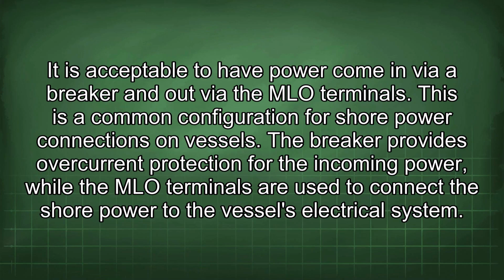It is acceptable to have power come in via breaker and out via the MLO terminals. This is a common configuration for shore power connections on vessels. The breaker provides overcurrent protection for the incoming power, while the MLO terminals are used to connect the shore power to the vessel's electrical system.